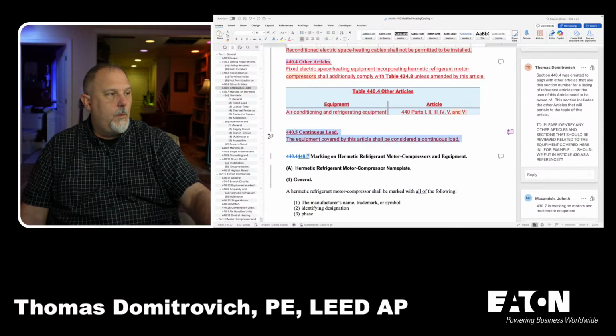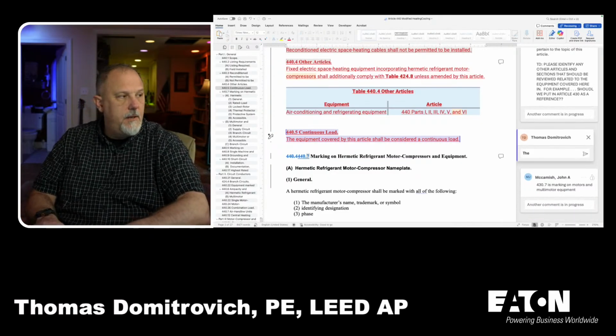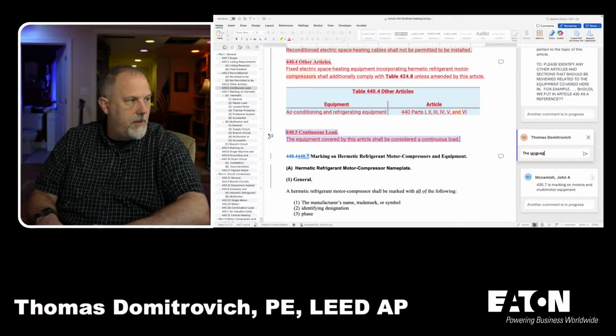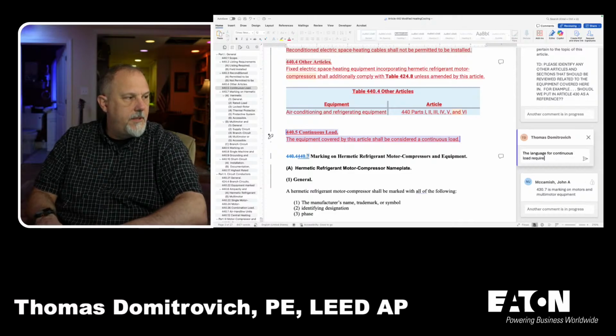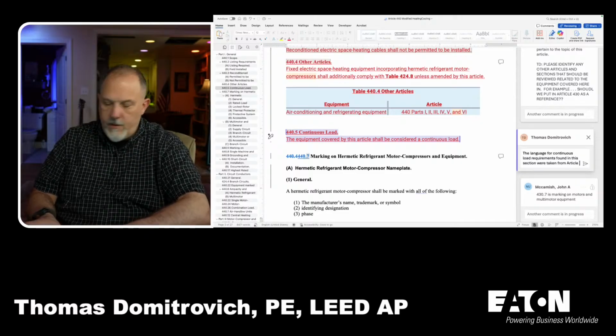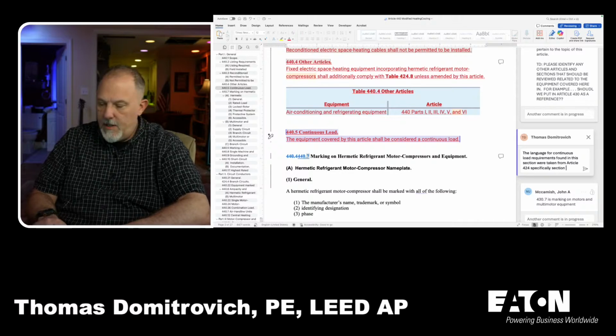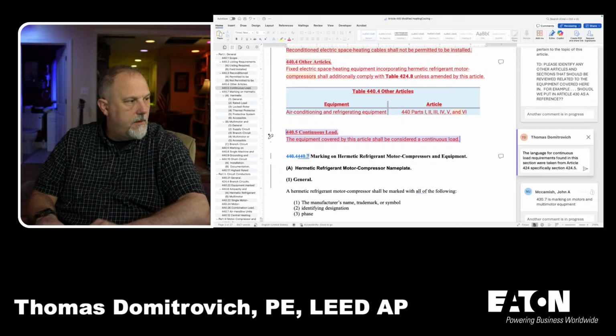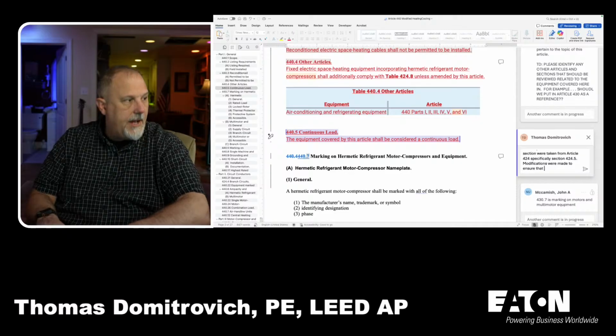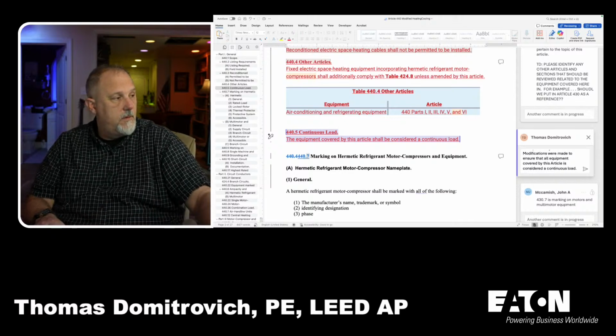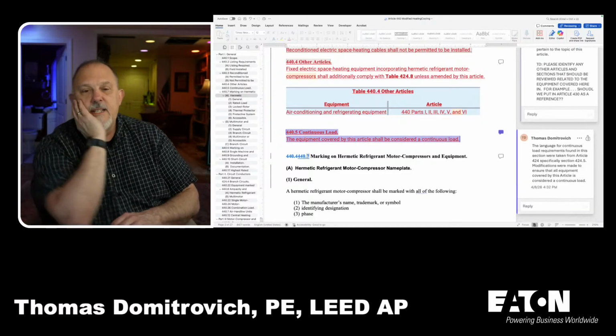I'm going to do this. The language for continuous load requirements found in this section were taken from Article 424, specifically Section 424.5. Modifications were made to ensure that all equipment covered by this article is considered a continuous load. Make sense? That's good.